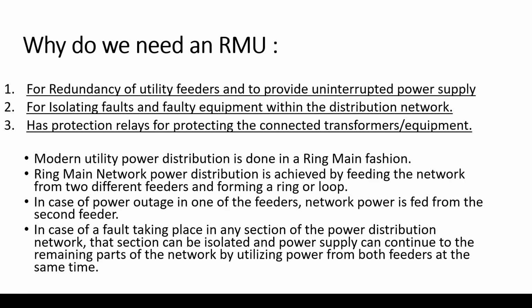Plus also, if any fault happens at any of the equipment, for example a transformer, you would be able to isolate that transformer. You would simply disconnect it from the ring network without any downtime to the other loads in the same network. So I would be able to disconnect any faulty equipment. It's like I have a tapping point to the 11 kV network, or to the network, whatever voltage it is, through the RMU. The RMU is like my tapping point to the available ring from the utility. So I can easily disconnect it and isolate it from the network.